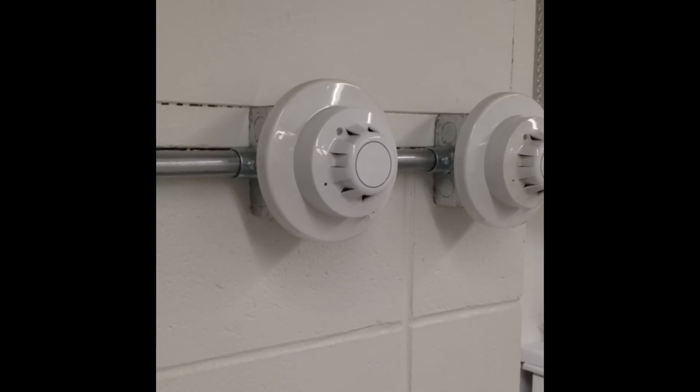Fire alarm system smoke detectors are required by NFPA 72 to be functionally tested once a year. The purpose of a functional test is to verify that the detector operates when smoke enters the detector chamber.